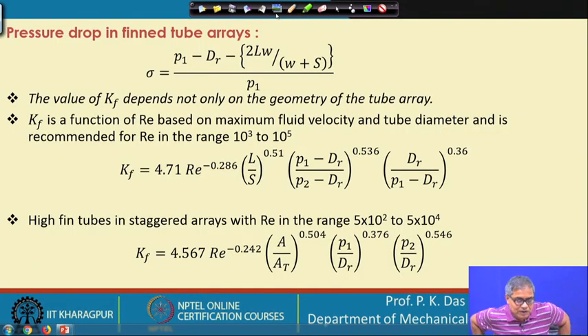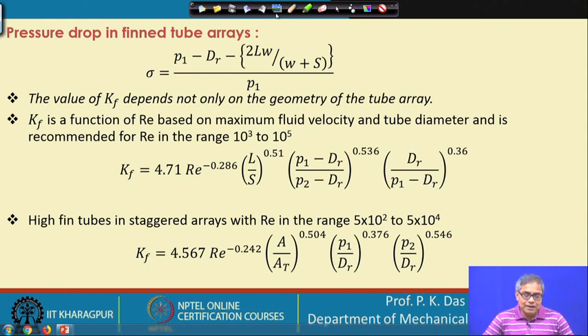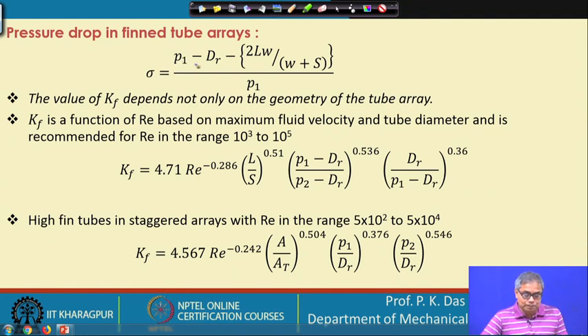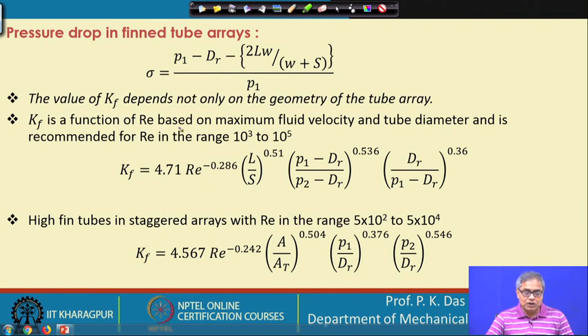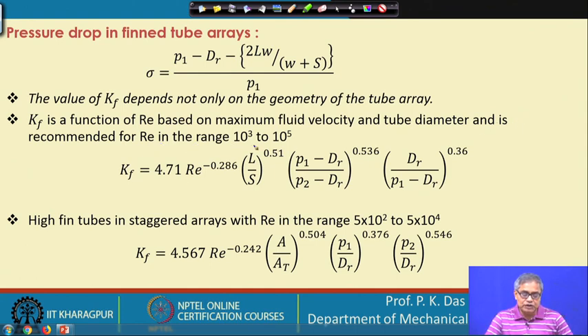Now we can understand what is in the slide. Sigma is calculated from the tube array pitch. One pitch, the root diameter of the fin, the height of the fin, the width of the fin, and the space between two fins all come into the formula. The value of K_f depends not only on the geometry of the tube array but also on other factors. K_f is a function of Reynolds number based on maximum fluid velocity and tube diameter, and is recommended for Re in the range of 10³ to 10⁵.